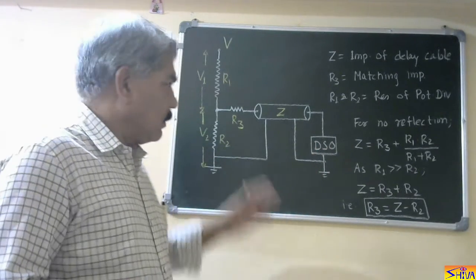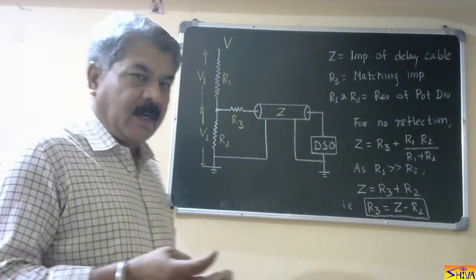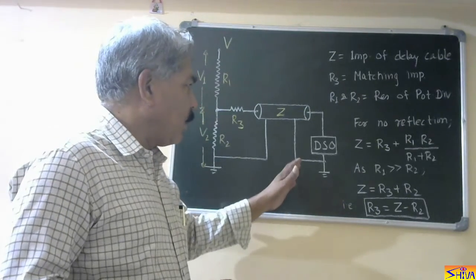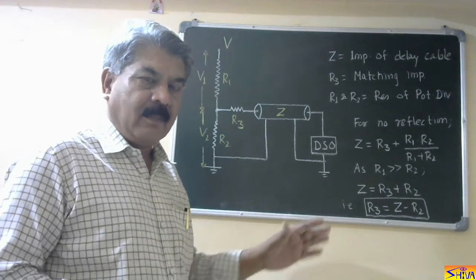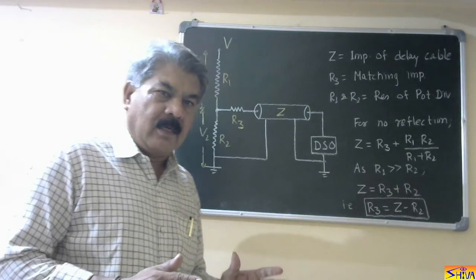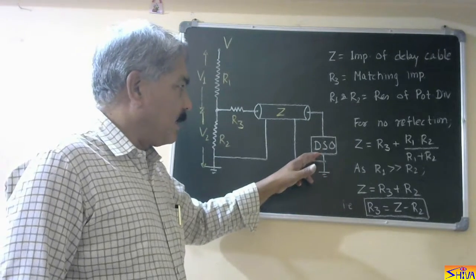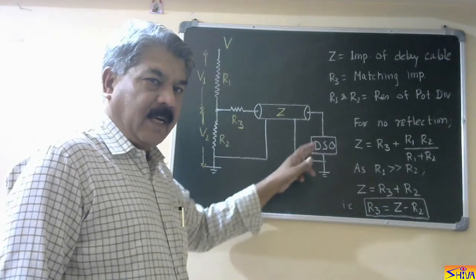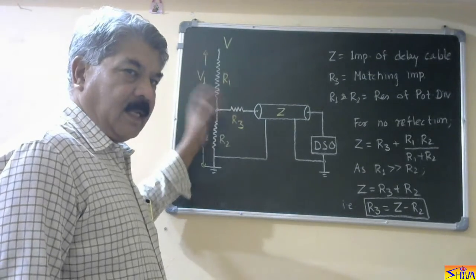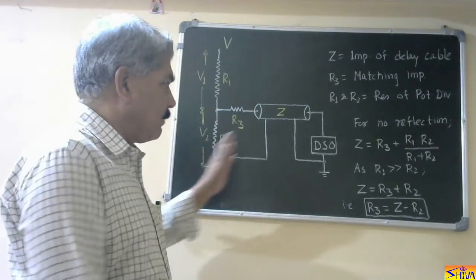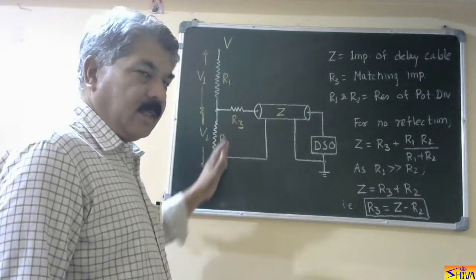So, either this complete assembly — that is impulse generator, test object, and this potential divider — will be in a Faraday cage, and the operating personnel, that is control panel and this DSO, will be outside the Faraday cage. This normally happens in an institutional laboratory. But in some labs, the operating personnel, measuring arrangement — that is digital storage oscilloscope and control panel — are in the Faraday cage, whereas the impulse generator, divider, and test object are outside the Faraday cage. So in both cases, the operating personnel, control panel, and DSO are far away from this high voltage test setup.